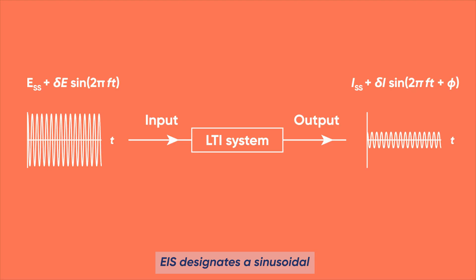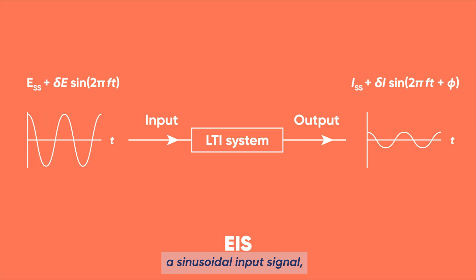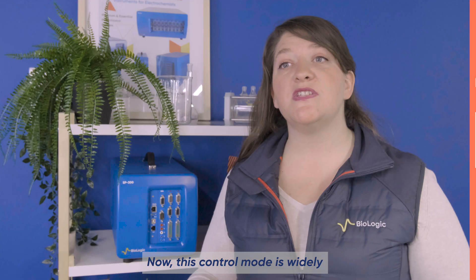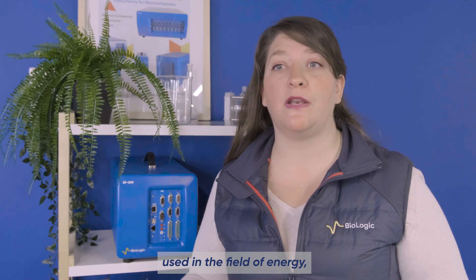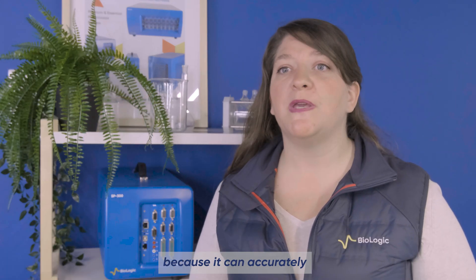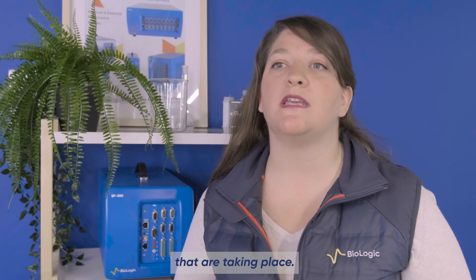EIS designates a sinusoidal or AC control mode. The potentiostat applies a sinusoidal input signal — either current or voltage — at various frequencies, and then measures the dynamic response of the system. This control mode is widely used in the field of energy, such as batteries and fuel cells, and for corrosion, because it can accurately and rapidly provide a detailed description of the system and the mechanisms of the electrochemical reactions taking place.